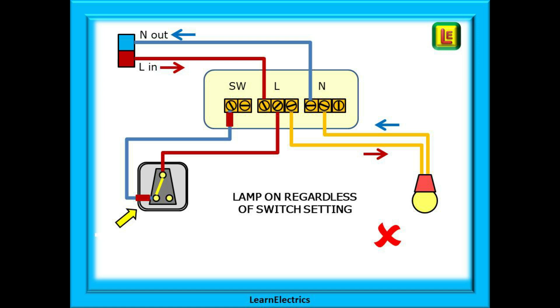I've had this problem a few times especially after the customer has decorated. They've taken the pendant fitting off whilst they papered the ceiling or fitted a new ceiling rose and then put the wires back where they thought they should go. Putting the switch in the opposite setting makes no difference. The lamp, the pendant wire, is not connected to the switch block. It has been connected to the permanent live. The lamp is permanently energised. Whenever the lighting circuit breaker is on, the lamp will be on. The solution? Isolate the circuit, then move the pendant wire from the live loop to the switch block.